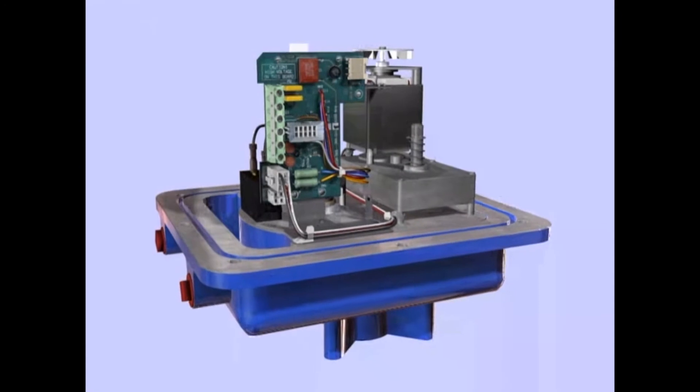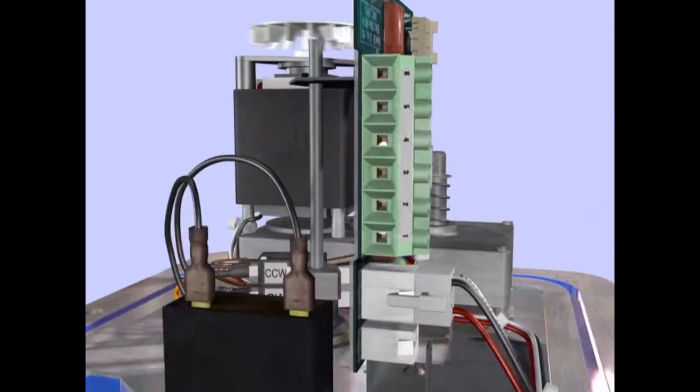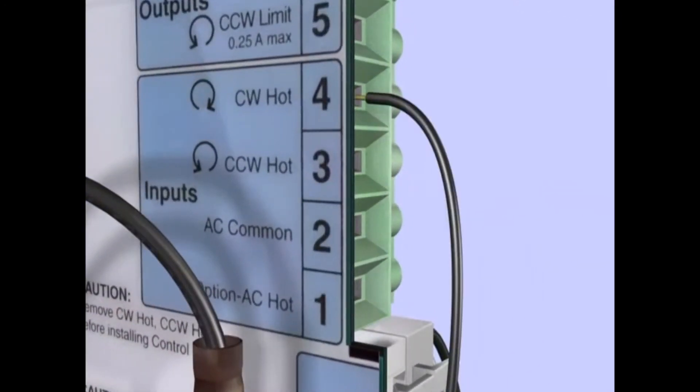Begin by connecting input wires. Connect a hot signal to Terminal 4 for clockwise operation, a hot signal to Terminal 3 for counterclockwise operation, and a neutral to Terminal 2.